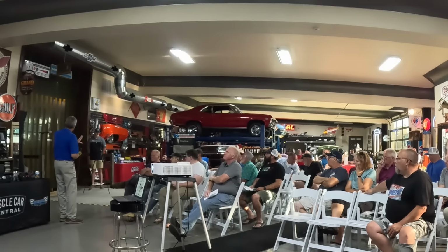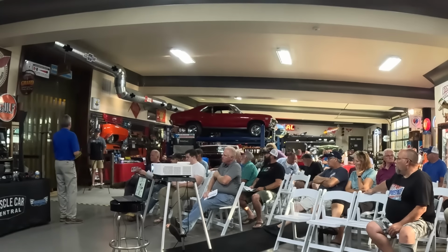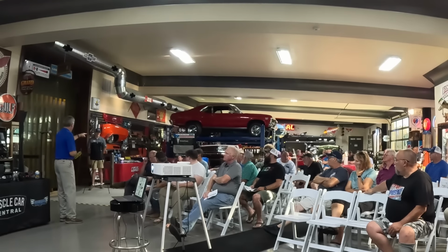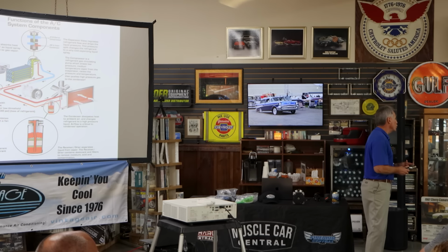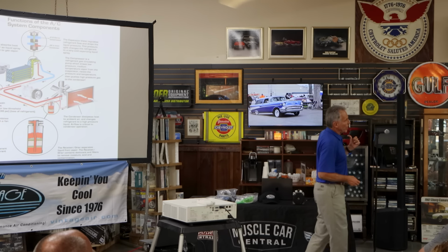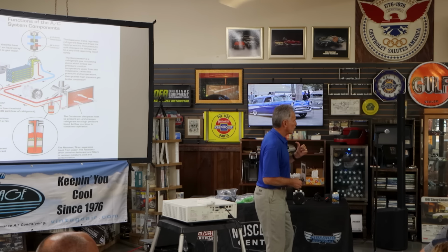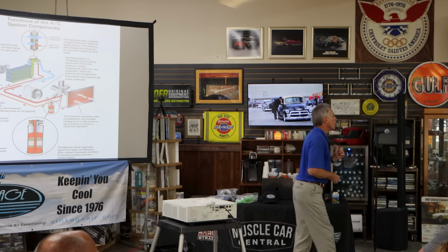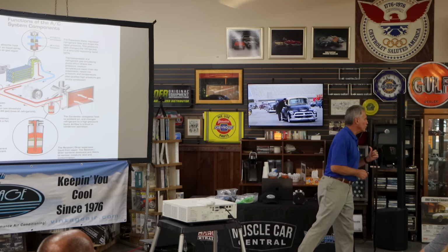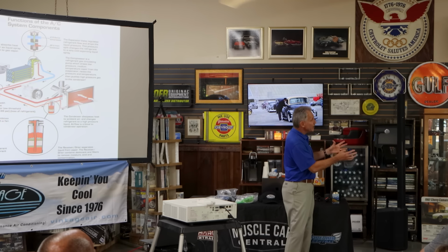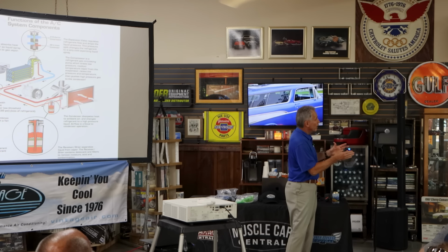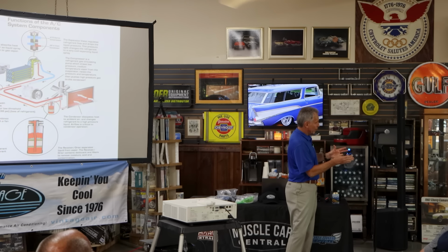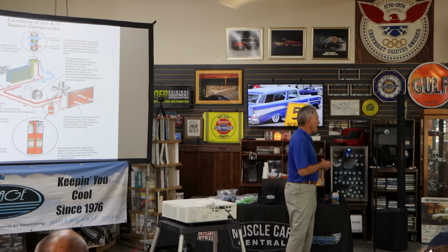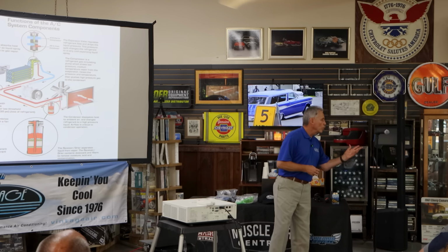But my first thing was, how does it know? Well, it knows because you got a pressure transducer there. You're basically doing what a trinary does, just with another part called a pressure transducer. You're feeding that computer input information, and then you can set when it engages the fan from that.